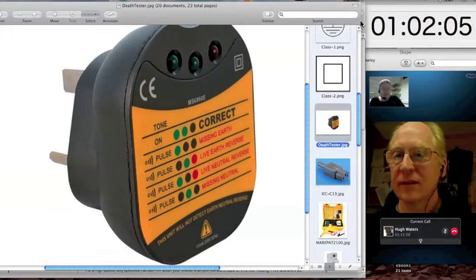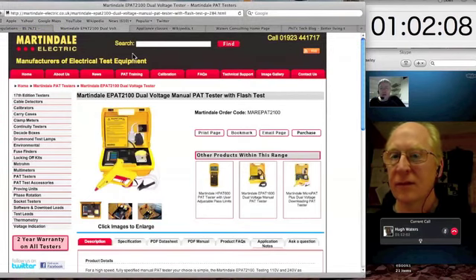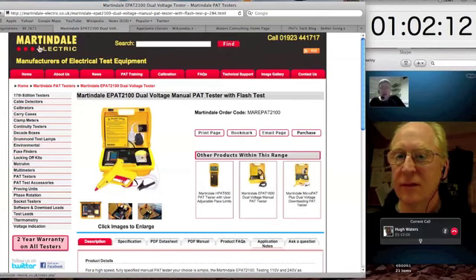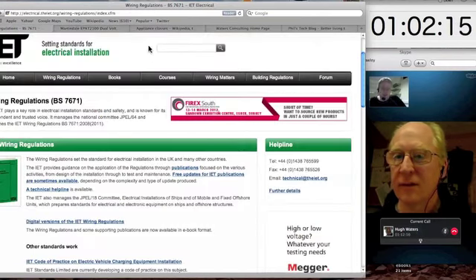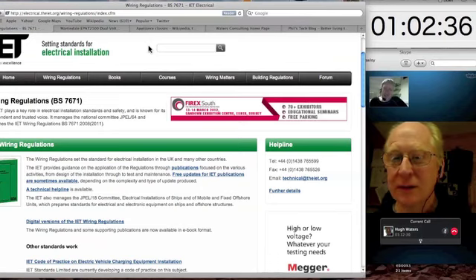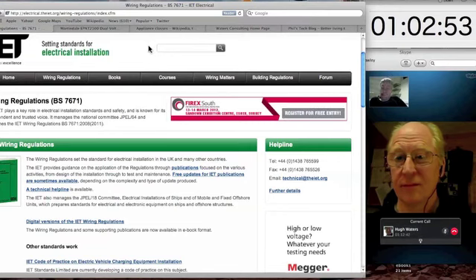Interestingly, electrical safety is one of those things where you can be summarily dismissed on the spot for putting a customer's life at risk. We had an engineer whose responsibility it was to do all the electrical safety testing in a build. He told me on the Friday afternoon, "Yep, Chief, I've done it all, tested out fine." And on the Monday, when I was handing over to the customer, it looked like nobody had been there on the Friday. It looked like I remembered it from the Thursday night, and I thought, I'll just put my death tester on some of these supplies just to check. And I found a couple of faults, earth neutral swaps, that kind of thing, which in an extreme case could have injured a customer. And in that position, you have no other option than to let the person go, and we did. And the union isn't going to back you up on that one.